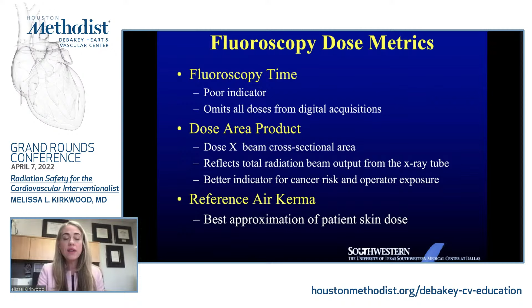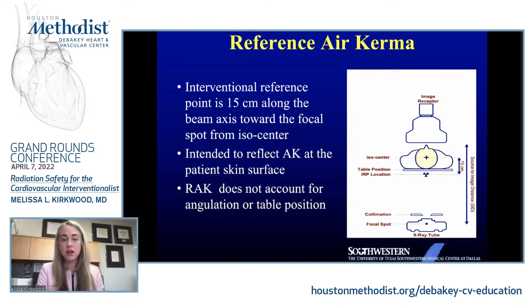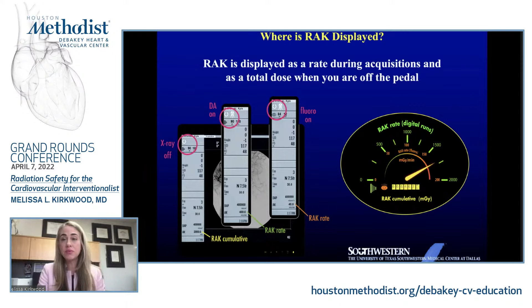The reference air kerma is just the dose at a reference point. So the interventional reference point is 15 centimeters along the beam axis towards the focal spot from isocenter. So it sits appropriately where the patient's skin should be for an average size 70 kilogram patient. So obviously, if the patient is larger, the skin dose doesn't exactly mirror the RAK. So where is RAK displayed? So RAK is displayed as a rate when you're on the pedal and as a total dose when you're off the pedal. So it's important to keep track of both those numbers throughout your procedure.